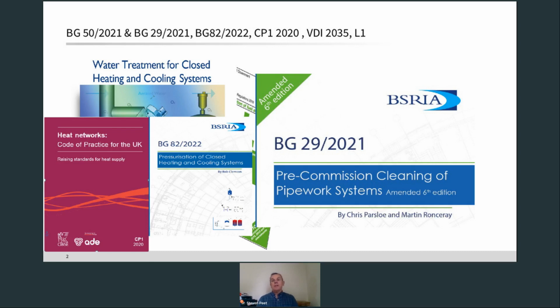So really, in summarizing this guidance, it suggests if the first 4 key elements of the water treatment program are addressed, i.e. the hardness controlled, corrosion inhibited, pressure maintained and particulate contamination minimized, then there shouldn't be any barrier to effective microbiological treatment, and thus avoid the risk of not only Legionella proliferation but poor water quality. It suggests that if any of the first 4 elements of the treatment program are inadequate, the effectiveness of the biological treatment and therefore water quality may be impaired. So it's really necessary to have a combined approach to tackling all potential issues, leading to a better chance of long-term system integrity.